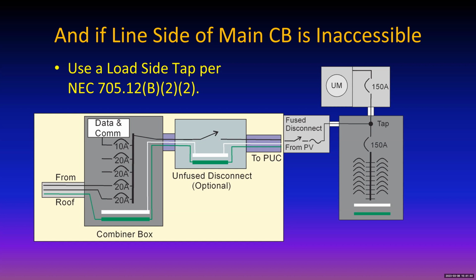All right, so here's your line side tap, and that's our load side tap. I don't know what fraction of our total jobs have load side taps, but I'd say maybe 20%. And it's when nothing else seems to work. There are times when you may have a main lug only distribution panel down there where you can't add that extra 150 amp breaker. So then you add another panel where you can add that 150, and you go from the meter down to the new panel and then out from the lugs on the bus bar to the original panel.